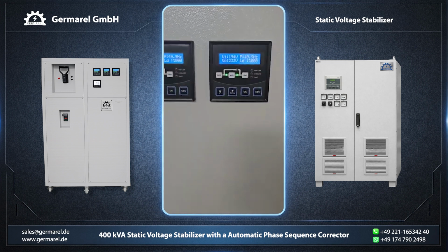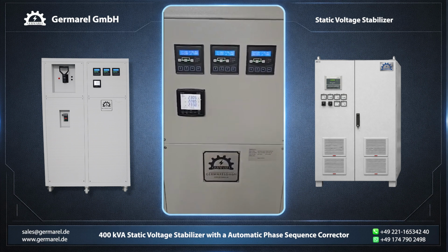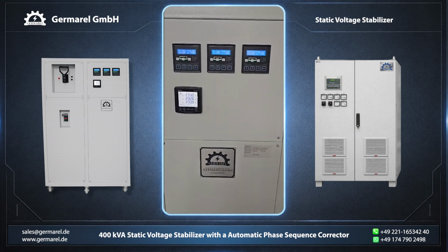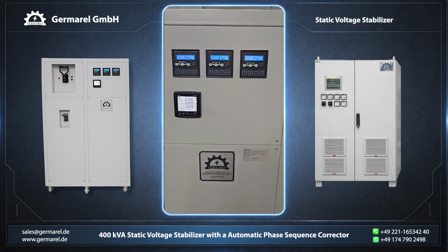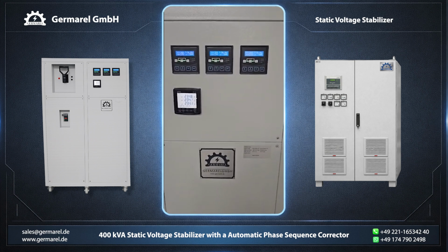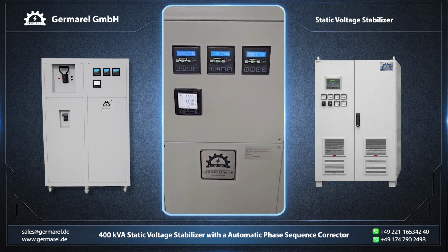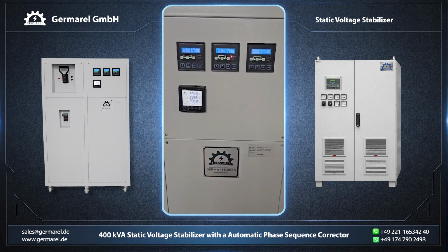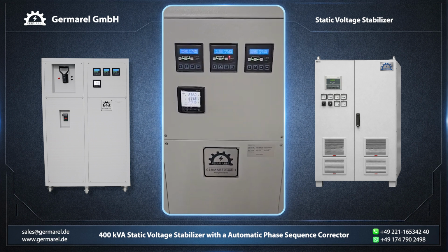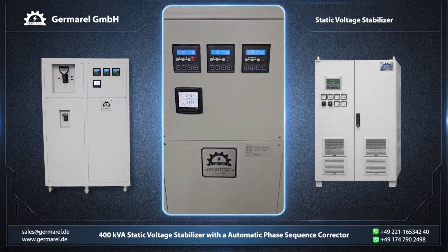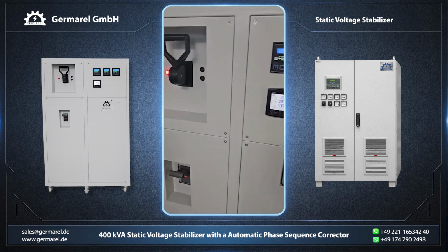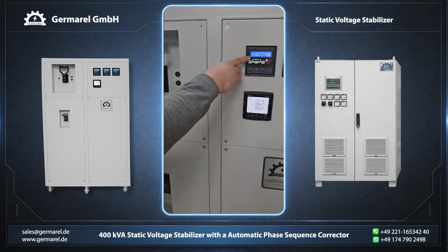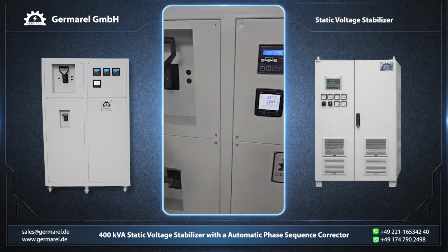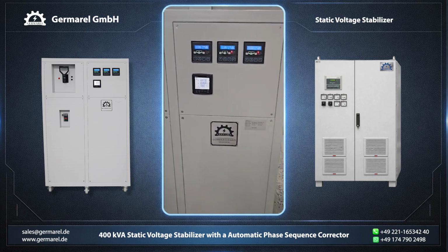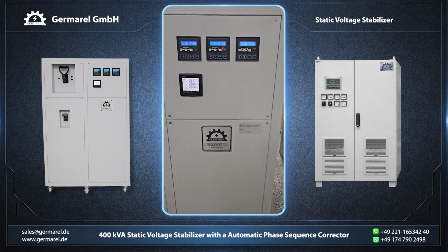The device is now working operationally. And now I am increasing the input voltage to its high limit. Like this. The device is still in the tolerance range. One of the phases is just giving a warning now. And I increase it a little bit more. When the output voltage is out of limit, you can see the alarm is lit, and the contactor is now in the off position. There is no voltage output.